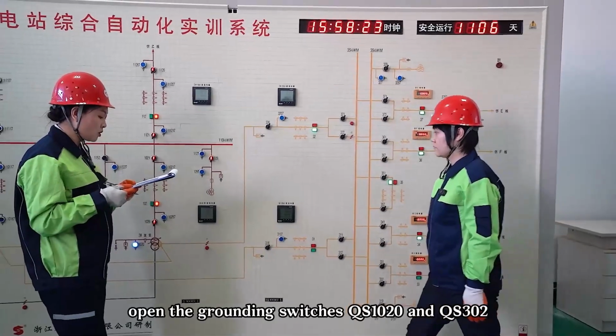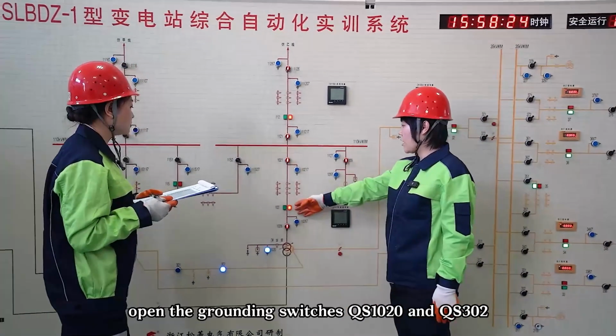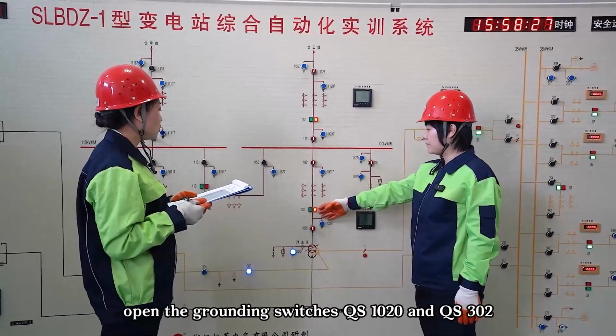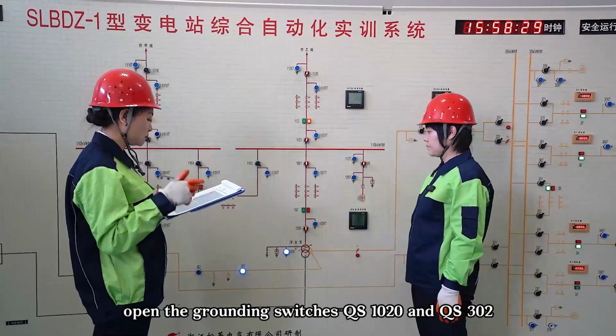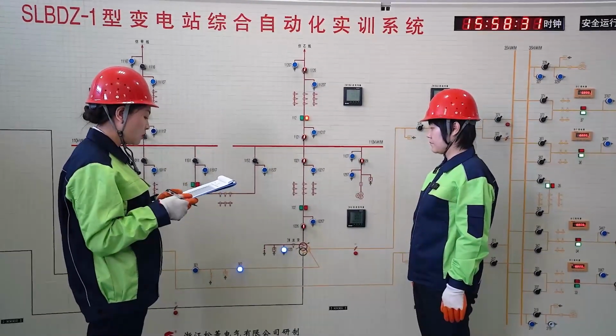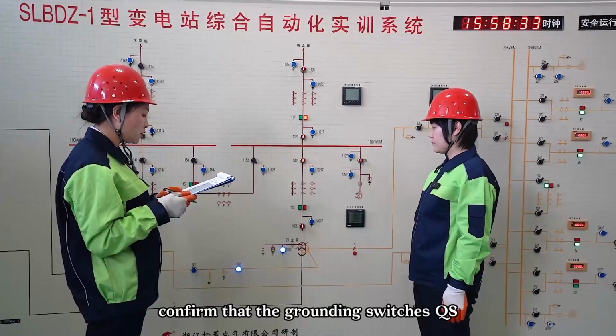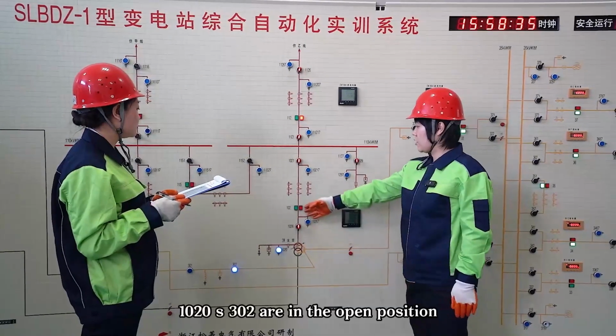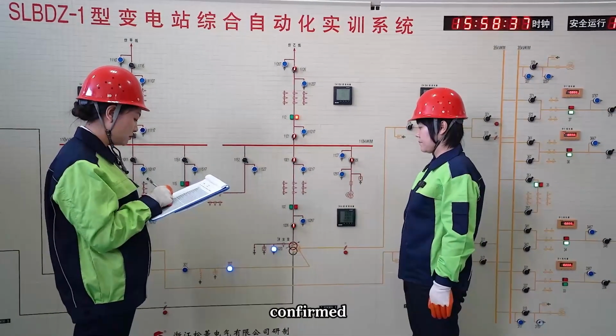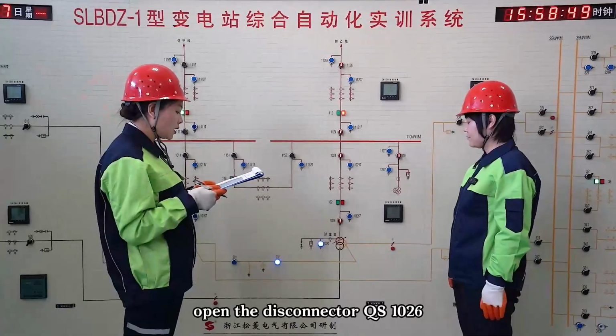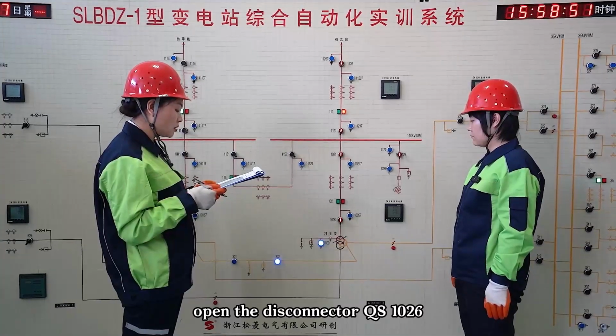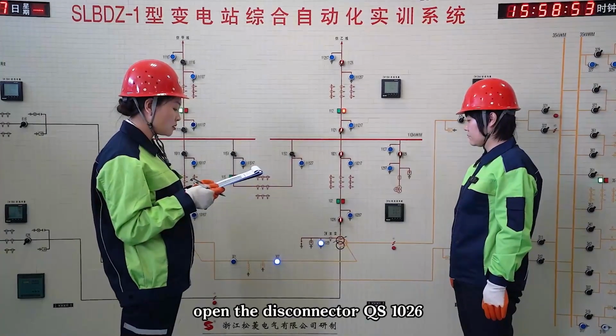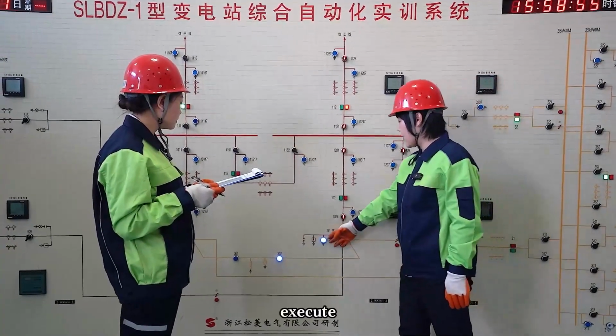Confirmed. Open the grounding switches QS1020 and QS302. Execute. Confirm that the grounding switches QS1020 and QS302 are in the open position. Confirmed. Open the disconnector QS1026. Execute.